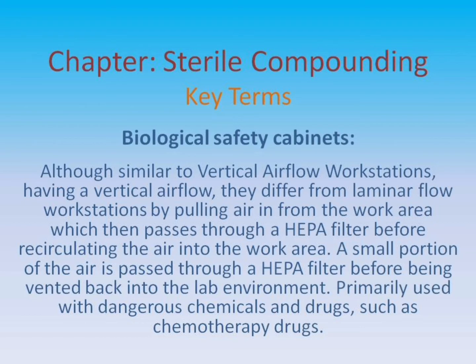Biological safety cabinets: although similar to vertical airflow workstations in having a vertical airflow, they differ from laminar flow workstations by pulling air in from the work area, which then passes through a HEPA filter before recirculating into the work area. A small portion of the air is passed through a HEPA filter before being vented back into the lab environment. Primarily used with dangerous chemicals and drugs, such as chemotherapy drugs.